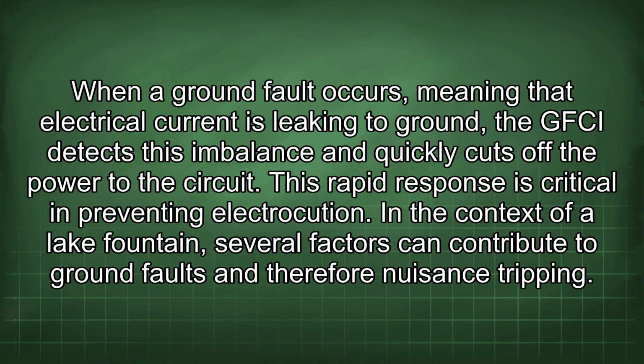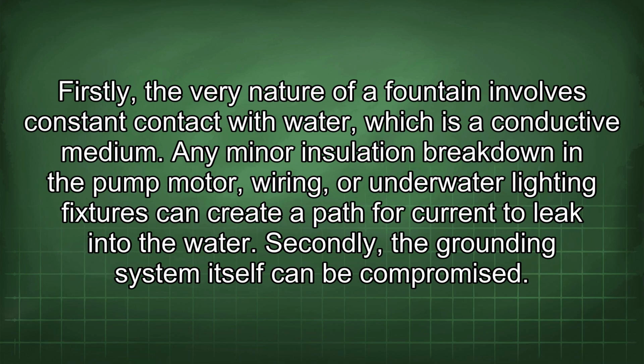When a ground fault occurs, meaning that electrical current is leaking to ground, the GFCI detects this imbalance and quickly cuts off the power to the circuit. This rapid response is critical in preventing electrocution. In the context of a lake fountain, several factors can contribute to ground faults and therefore nuisance tripping. Firstly, the very nature of a fountain involves constant contact with water, which is a conductive medium.